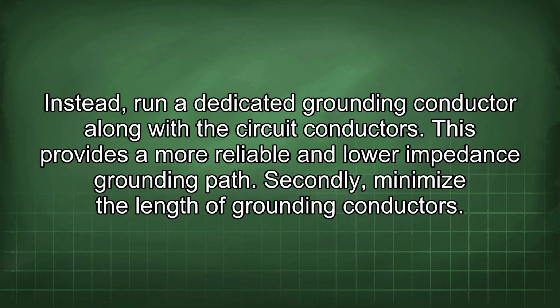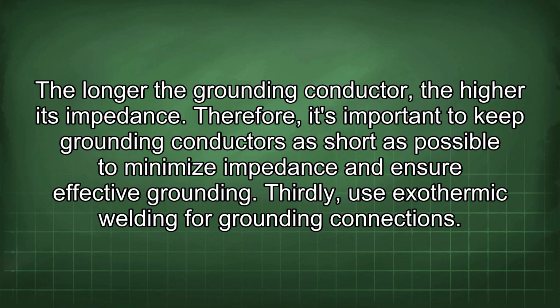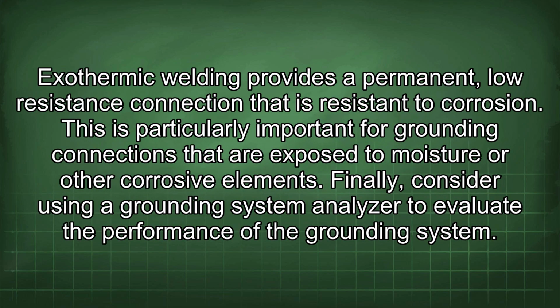Secondly, minimize the length of grounding conductors. The longer the grounding conductor, the higher its impedance. Therefore, it's important to keep grounding conductors as short as possible to minimize impedance and ensure effective grounding. Thirdly, use exothermic welding for grounding connections. Exothermic welding provides a permanent, low-resistance connection that is resistant to corrosion. This is particularly important for grounding connections that are exposed to moisture or other corrosive elements.